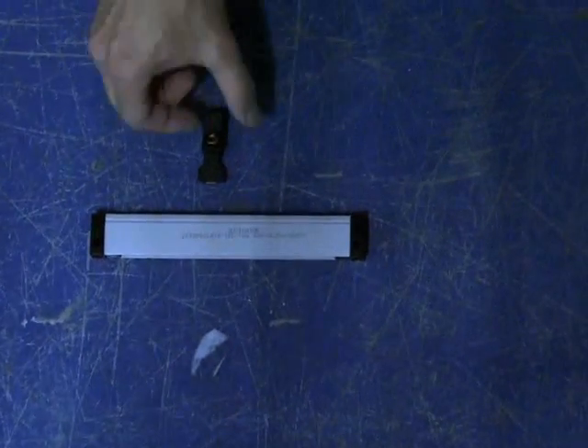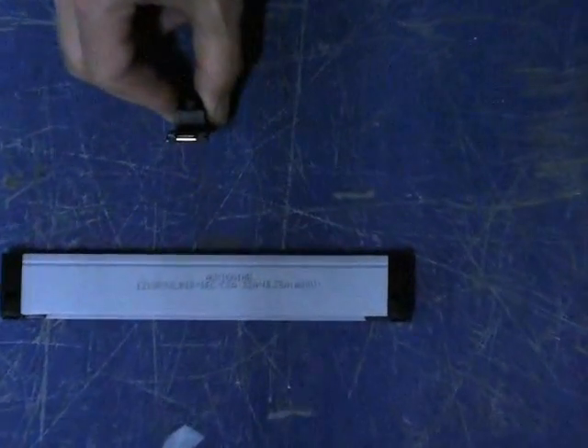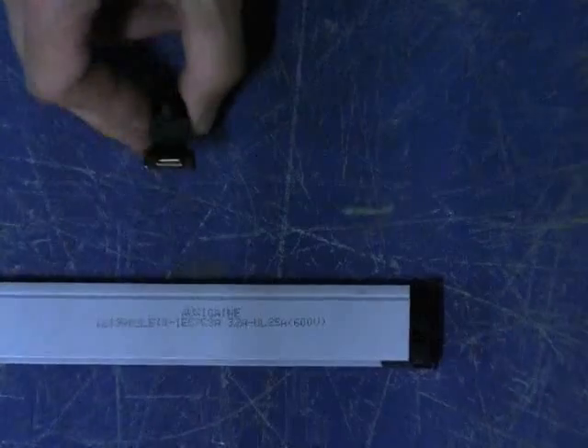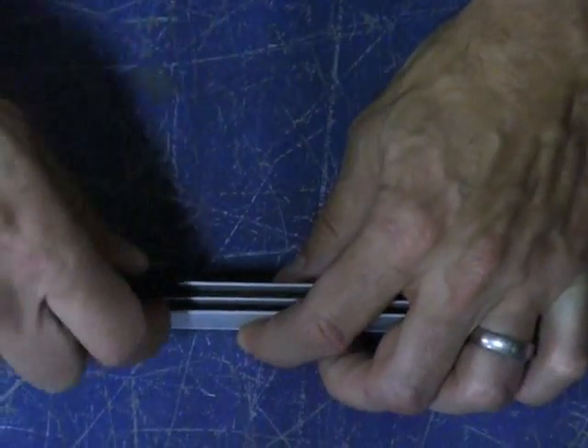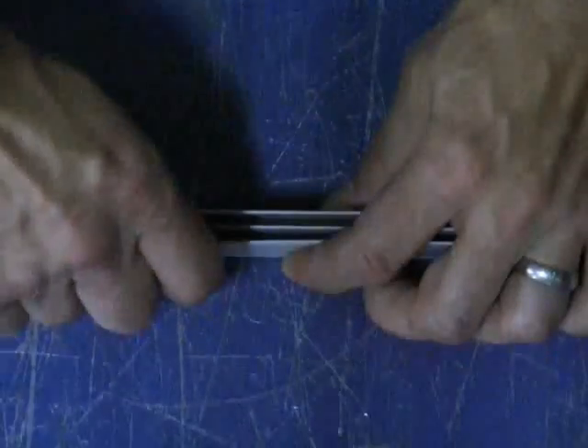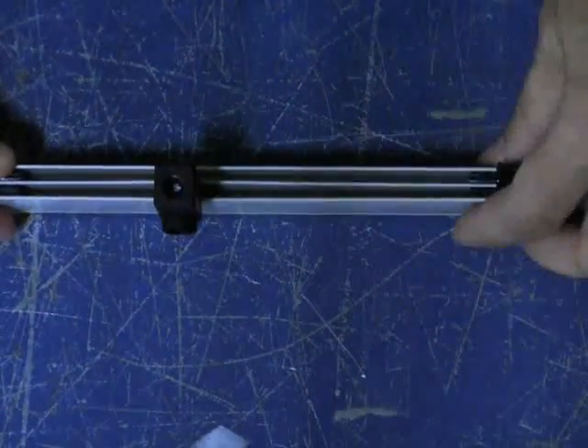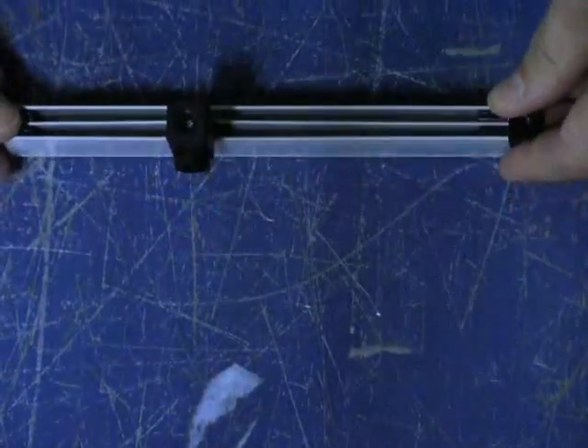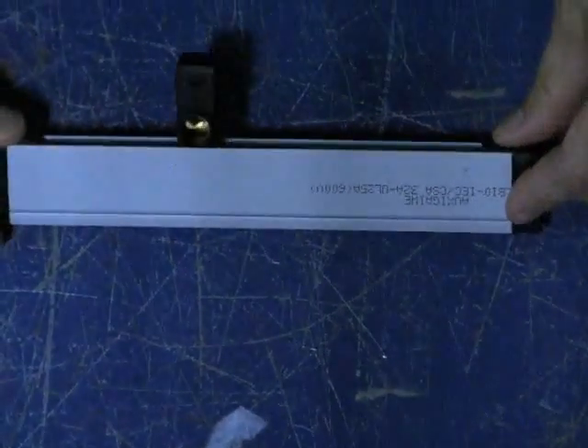The APD system comes with various accessories. Most importantly, the power input connector 40017. It can feed up to 90 amps to the busbars when center fed. The 40017 is difficult to push on to the tabs since its contacts are spring loaded to ensure good connectivity for 90 amps.